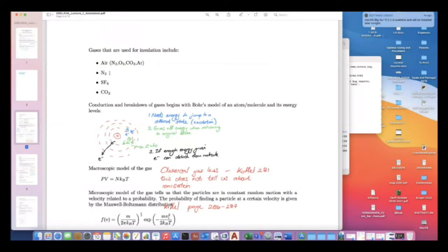Nitrogen, it's an insulator. SF6, this is called sulfur hexafluoride. It's a very good insulating gas. Unfortunately, it's pretty disastrous for the environment. So a lot of manufacturers are moving away from SF6. CO2, it's quite a good insulator. It's not as good as SF6. It's not as damaging to the environment as SF6.